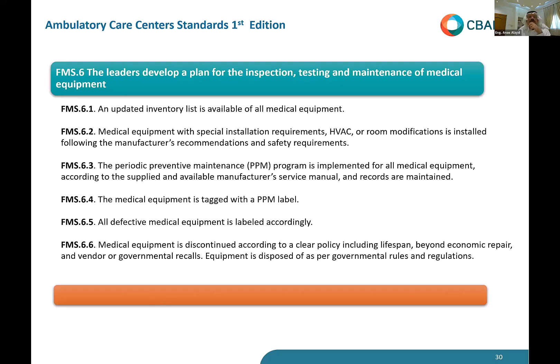Now, I always say this is very important: the life cycle of the medical equipment. This is the life cycle of the medical equipment. Whenever you have medical equipment coming to your center, make sure the bioengineering, either in-house or from your contractor, is checking it and doing a pre-checking on it. I don't rely on the manufacturers. When it has reached you, in Saudi Arabia, after shipping, somebody has to do a pre-issue check on it. So we don't rely on the manufacturer. When it has arrived at the location, somebody has to check.